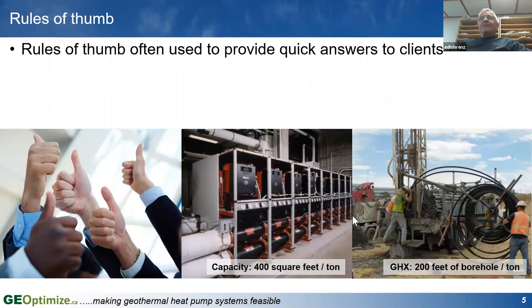The other is the amount of pipe that you need to put in the ground. A rule of thumb that's very often employed is that you need 200 feet of drilling per ton. That's going to change an awful lot whether you're drilling in limestone or granite, or whether you're drilling in clay, or whether you're drilling in silt. So it makes a huge difference.